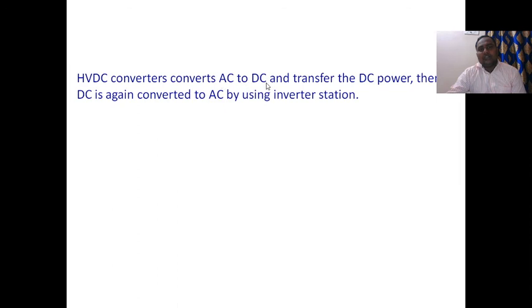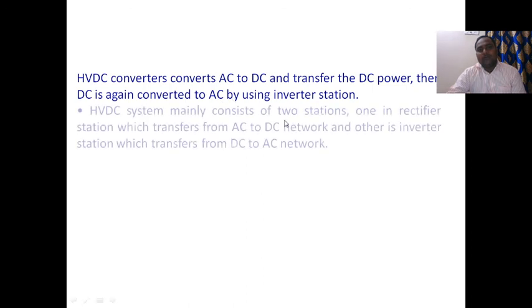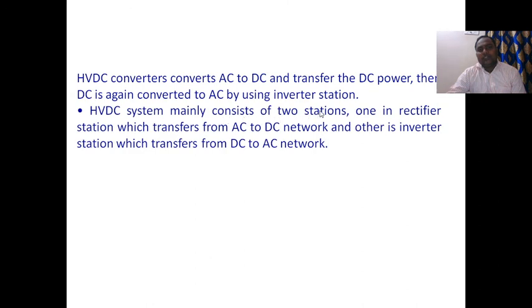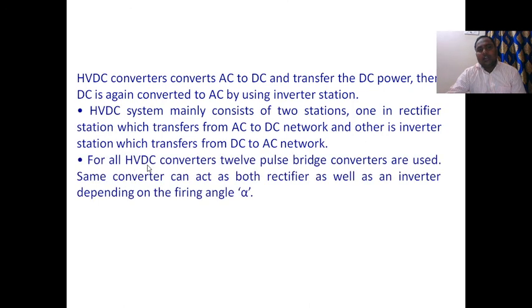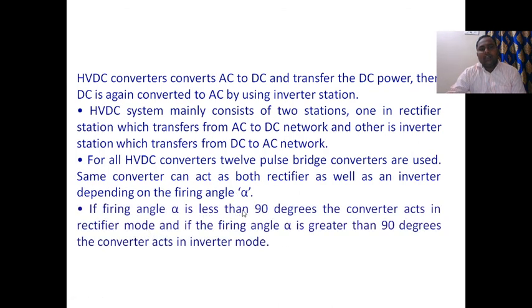An HVDC converter converts AC to DC and transfers the DC power. Then DC is again converted to AC by inverter stations. An HVDC system mainly consists of two stations. One is the rectifier station, which transfers from AC to DC, and the other is the inverter station, which transfers from DC to AC. For all HVDC converters, 12-pulse bridge converters are used. This 12-pulse is a combination of two 6-pulse bridge converters. Same converter can act as both rectifier and inverter depending upon the firing angle alpha. If the firing angle alpha is less than 90 degrees, the converter acts in rectifier mode, and if the firing angle alpha is greater than 90 degrees, the converter acts in inverter mode.